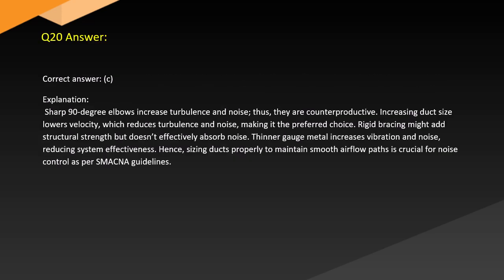Answer. Correct answer, C. Explanation. Sharp 90-degree elbows increase turbulence and noise, thus they are counterproductive. Increasing duct size lowers velocity, which reduces turbulence and noise, making it the preferred choice. Rigid bracing might add structural strength, but doesn't effectively absorb noise. Thinner gauge metal increases vibration and noise, reducing system effectiveness. Hence, sizing ducts properly to maintain smooth airflow paths is key for noise control as per SMACNA guidelines.